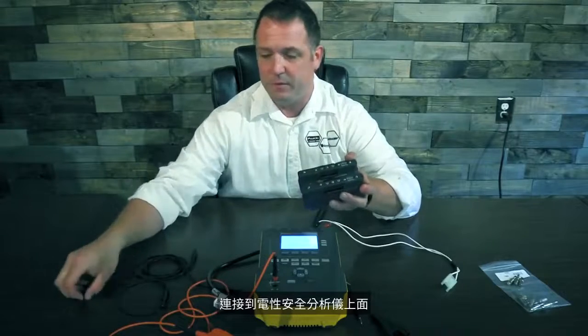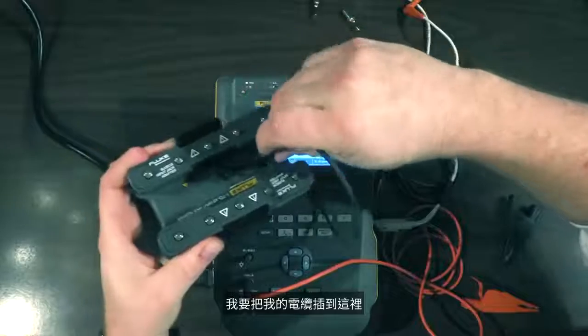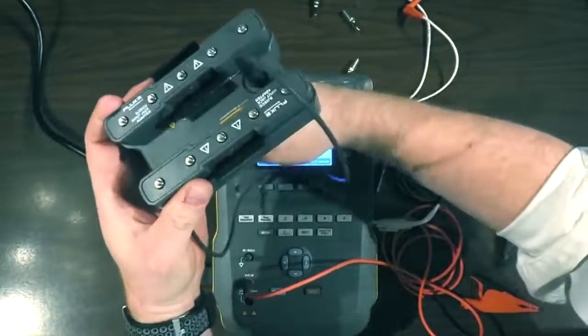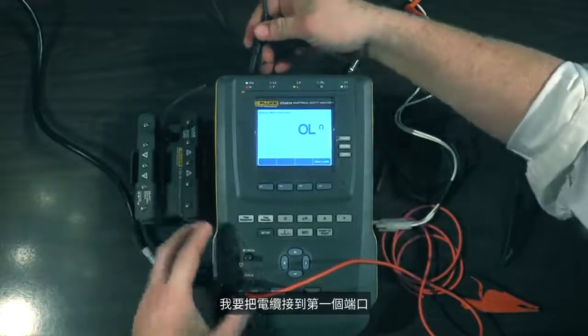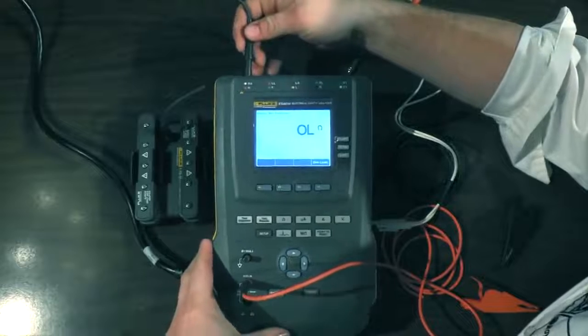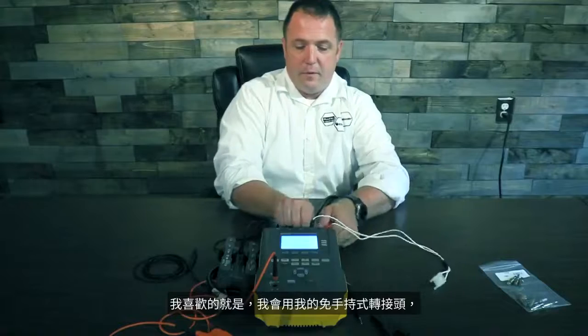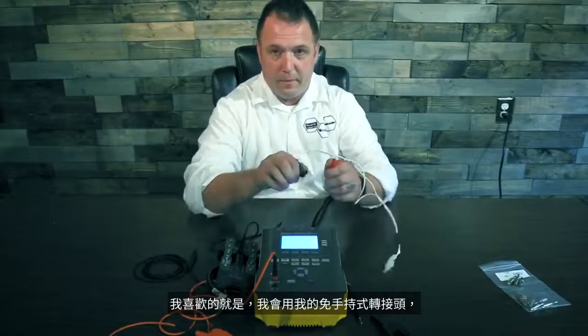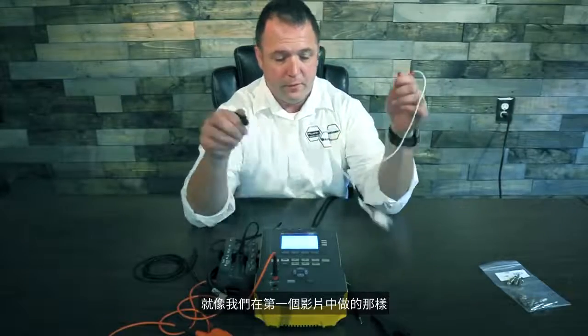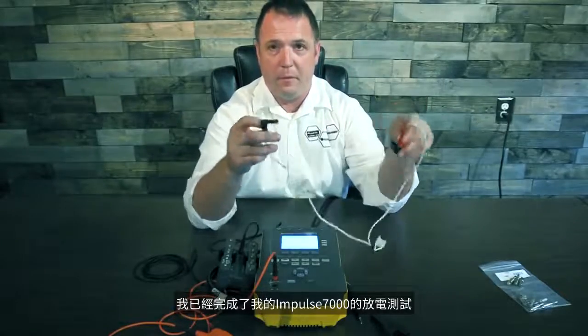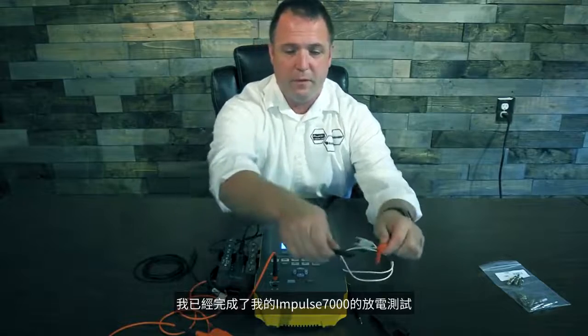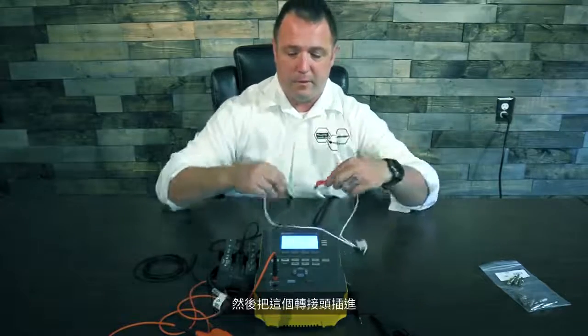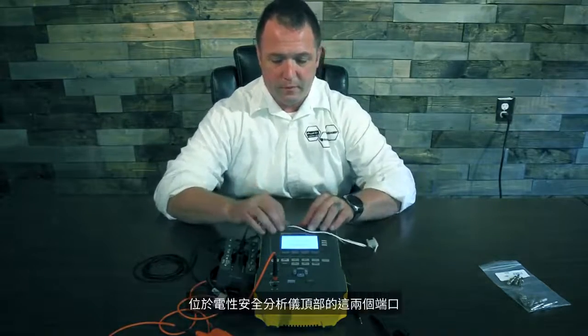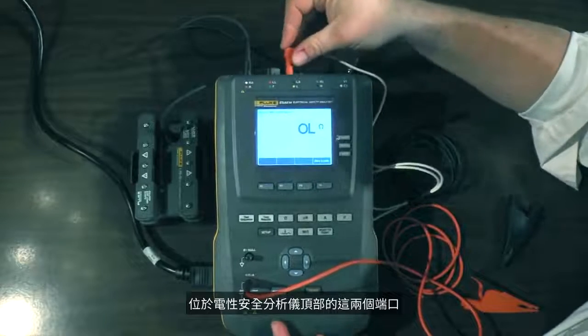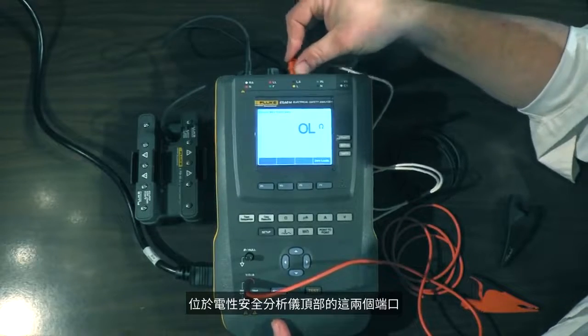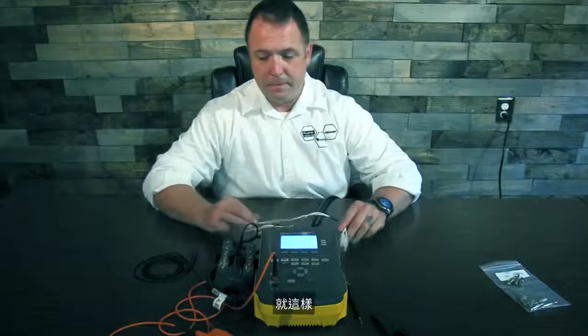the ESA at once. I'm going to simply take my cable and plug it into here. And we'll set that down here. And I'm going to take this into the first port. And then the way I like to do it is I'm going to take my hands-free adapter like we did in the first video. So this is going to be the hands-free adapter. I'm done with my discharge test with the Impulse 7000. I'm simply going to take this out and I'm going to plug this into these two ports on the top of the safety analyzer. There we go.